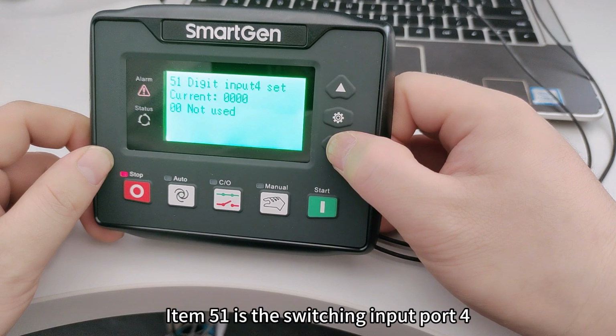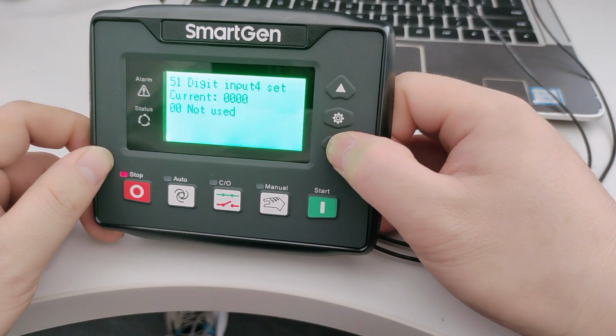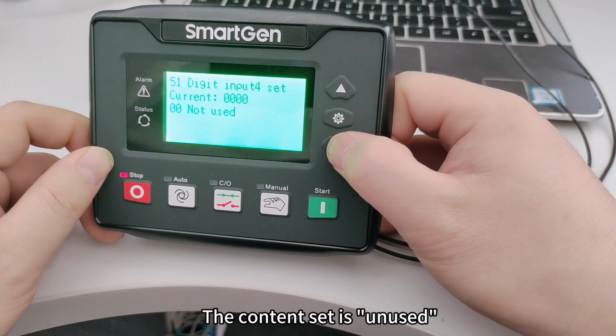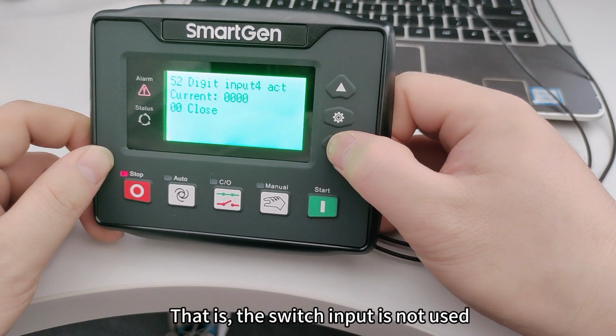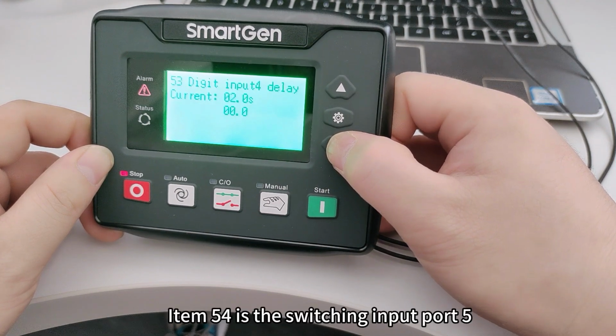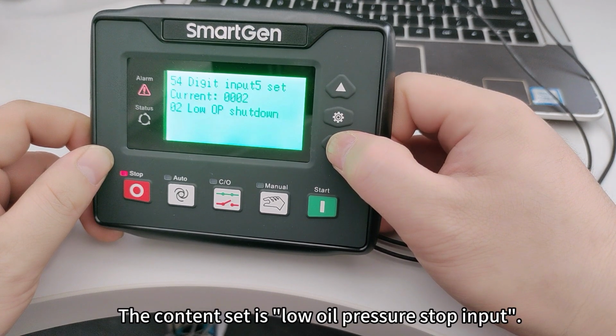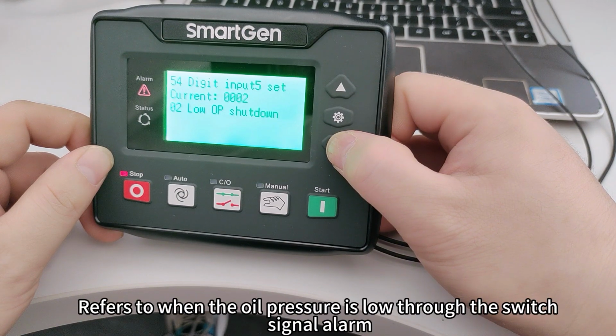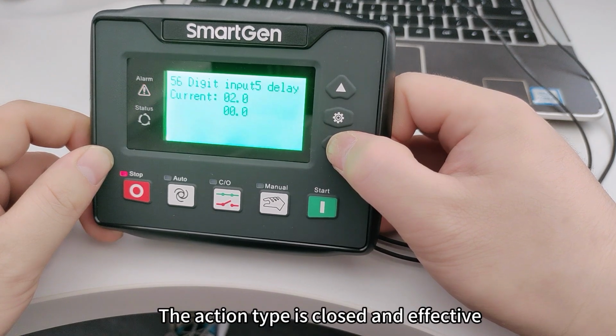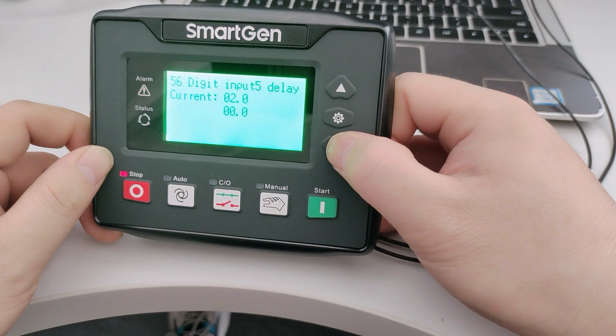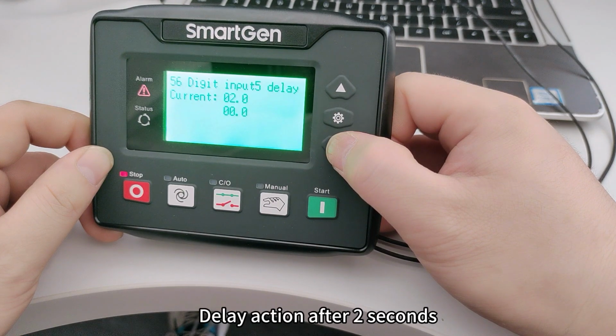Item 51 is the switching input port 4. The content set is unused, that is, the switch input is not used. Item 54 is the switching input port 5. The content set is low oil pressure stop input, which refers to an alarm through the switch signal when the oil pressure is low. The action type is closed and effective. Delay action after 2 seconds.